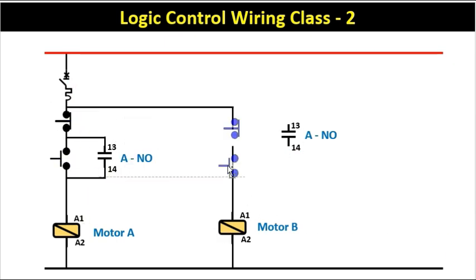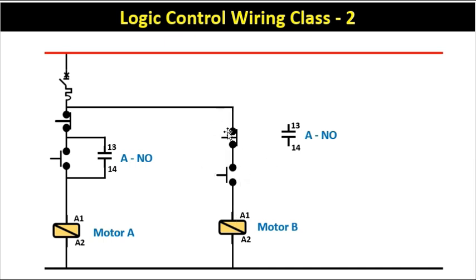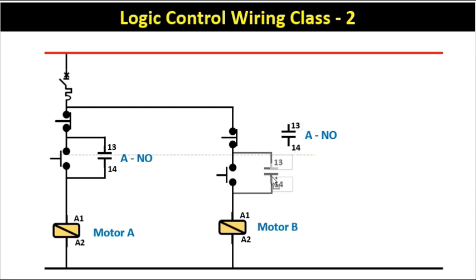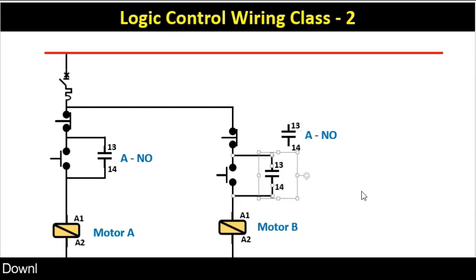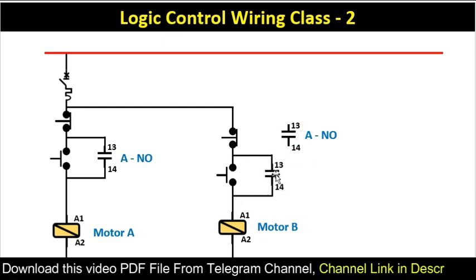Here I used one stop push button and one start push button. Through the stop push button we will turn off the motor, and through the start push button we will turn on the motor. We also need to hold this contactor, so we will make a holding circuit. The holding circuit is added, meaning the circuit to turn on and off motor B is now completed.